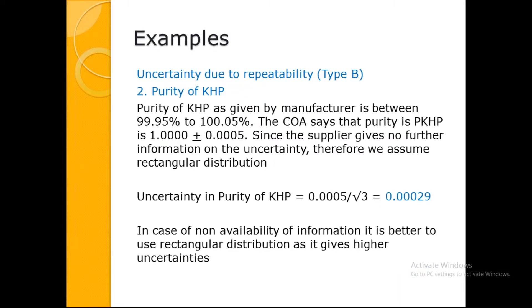The purity of KHP: the certificate states it is 1 plus or minus 0.0005, meaning 0.05 percent uncertainty. The manufacturer has not specified the distribution, so we assume rectangular distribution. We express 0.05 percent as 0.0005, then divide by square root of three. This gives the uncertainty due to purity of KHP. In the absence of information, it is better to use rectangular distribution as it gives higher uncertainties than triangular distribution.